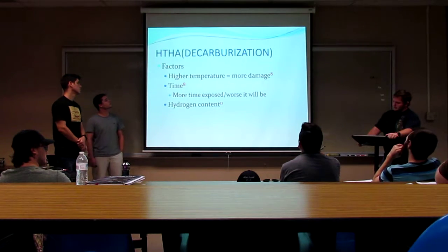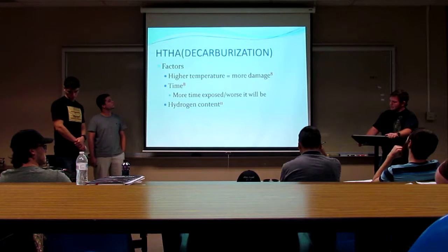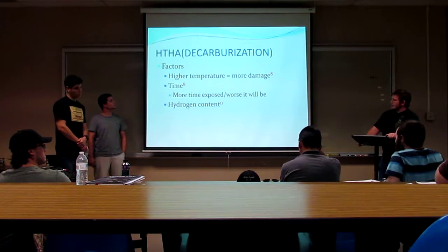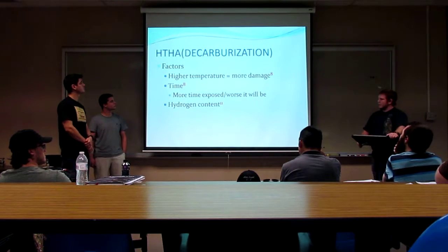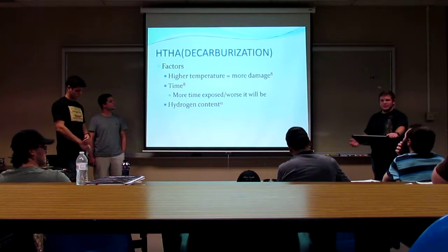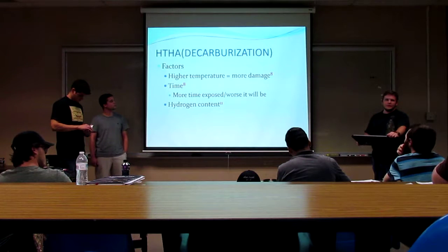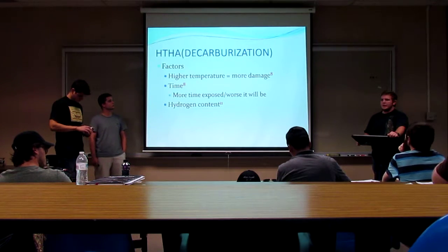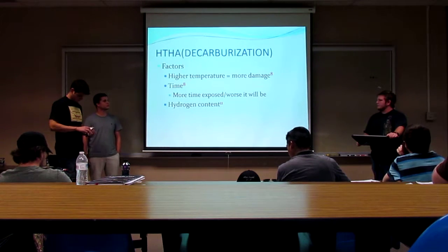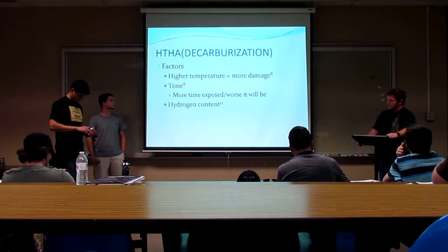Some of the factors that control it are the temperature: the higher the temperature, the more damage. The time: the more time exposed, the worse it'll be. That goes back to the time, temperature, pressure phenomenon. Then also the content of the hydrogen: the higher the content is, the more corrosive, the more damage it'll do to the structure.